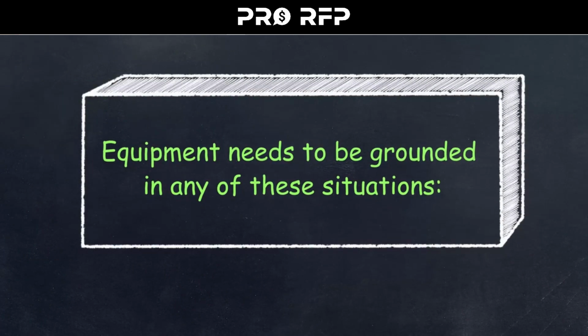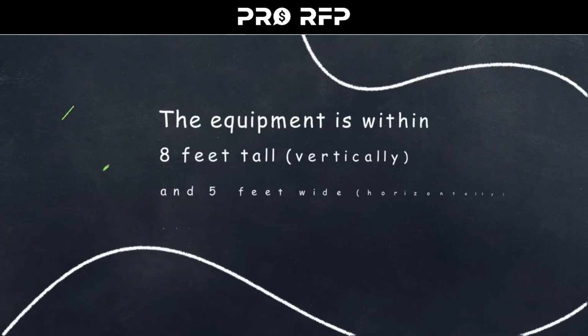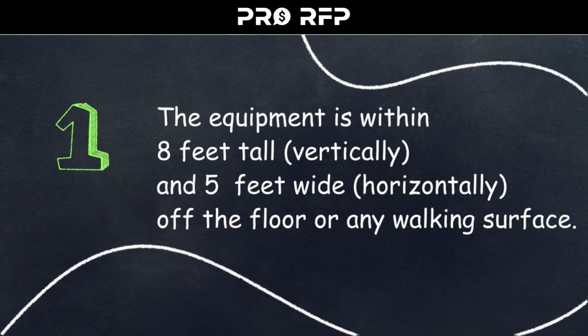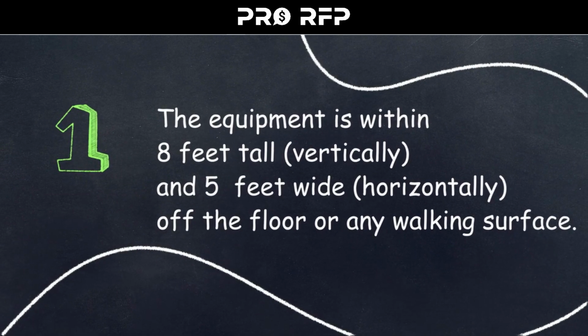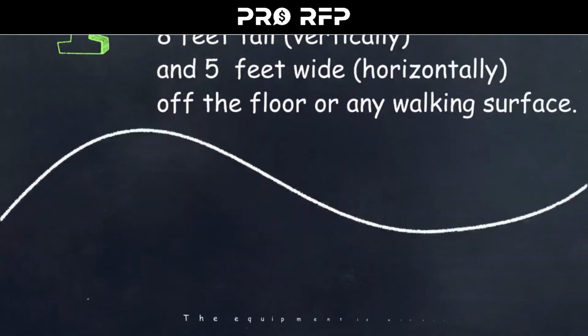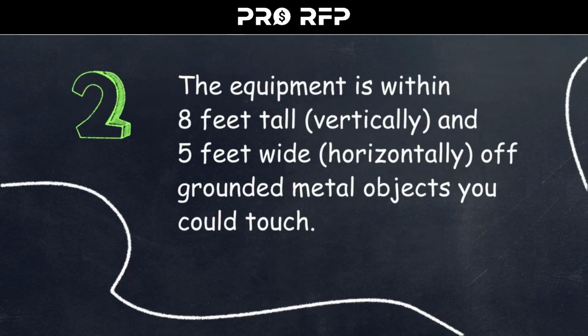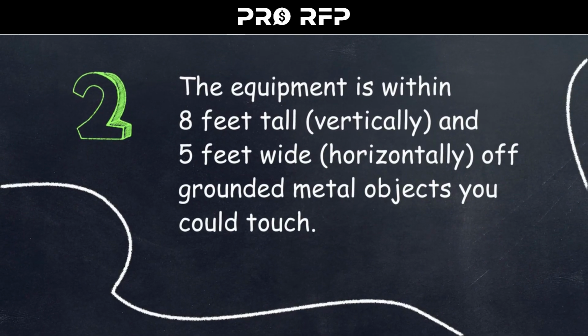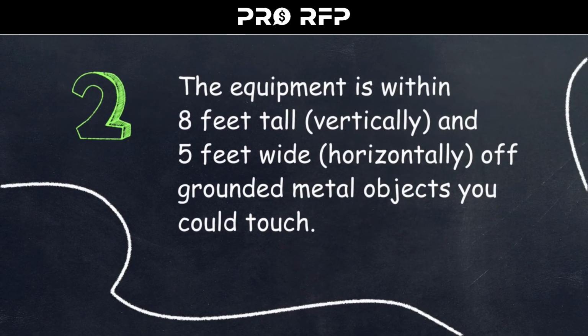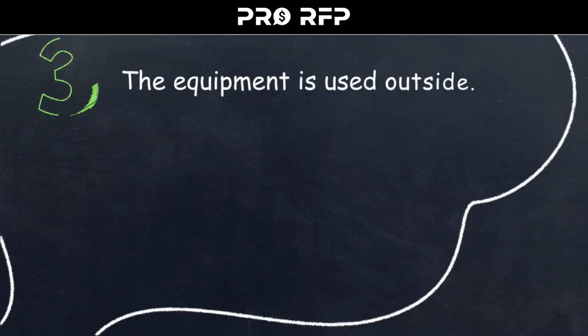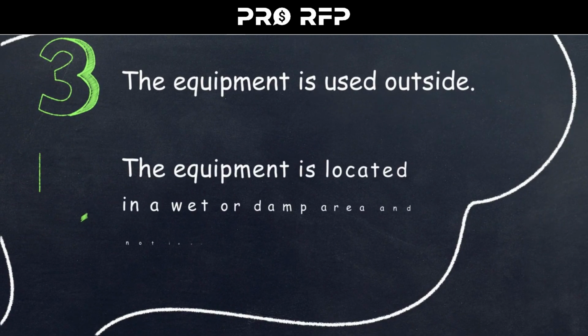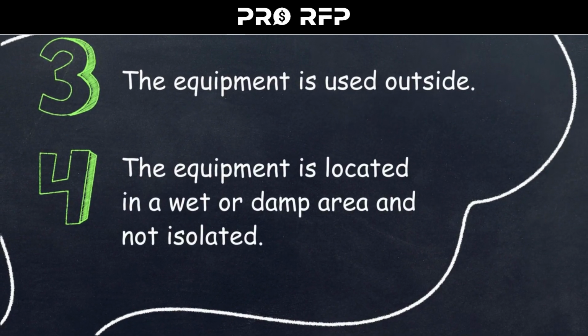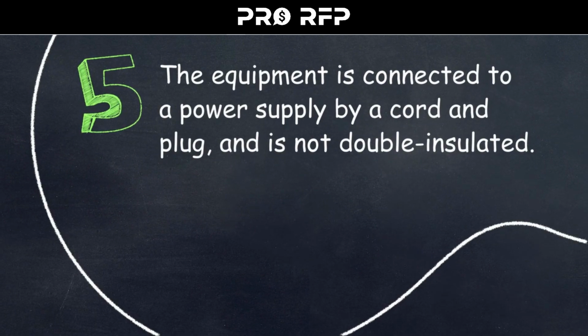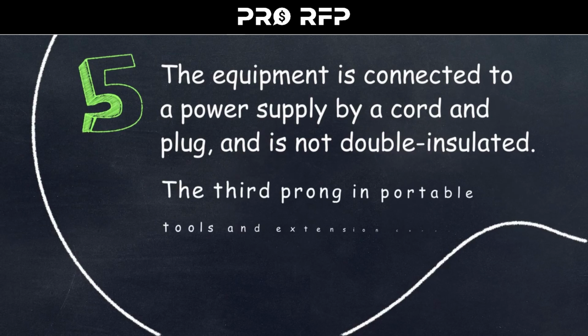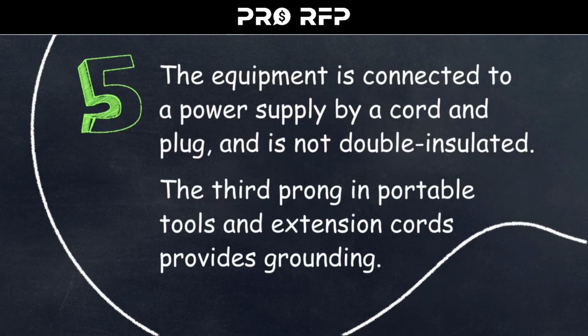Equipment needs to be grounded in any of these situations. The equipment is within 8 feet tall vertically and 5 feet wide horizontally off the ground or any walking surface. The equipment is within 8 feet tall vertically and 5 feet wide horizontally off grounded metal objects you could touch. The equipment is used outside. The equipment is located in a wet or damp area and not isolated. The equipment is connected to a power supply by a cord and plug and is not double insulated. The third prong in portable tools and extension cords provides grounding.